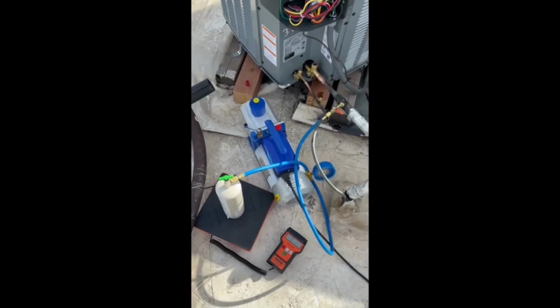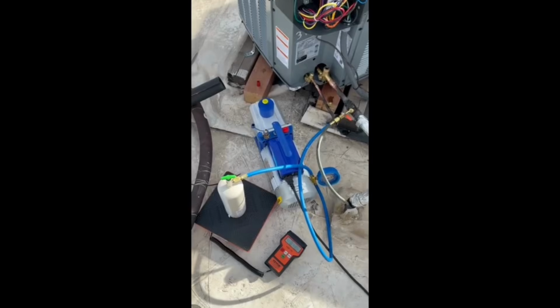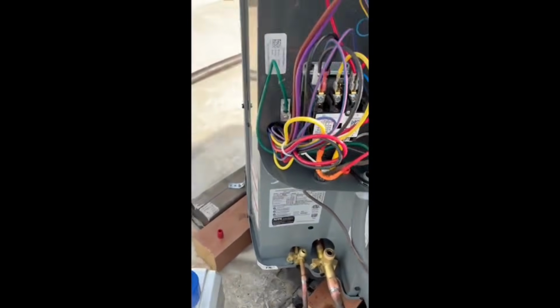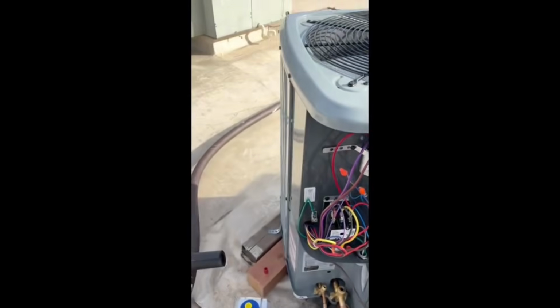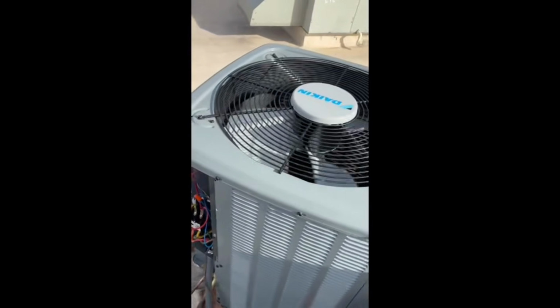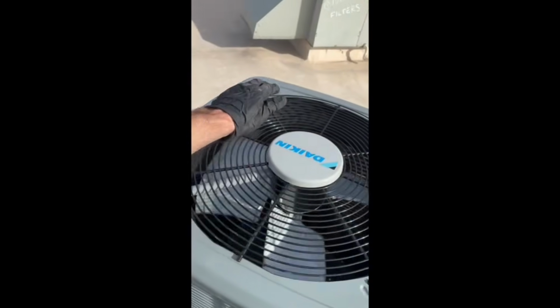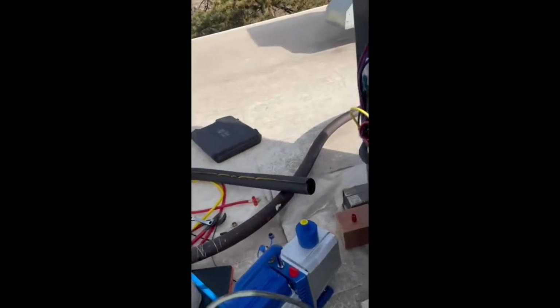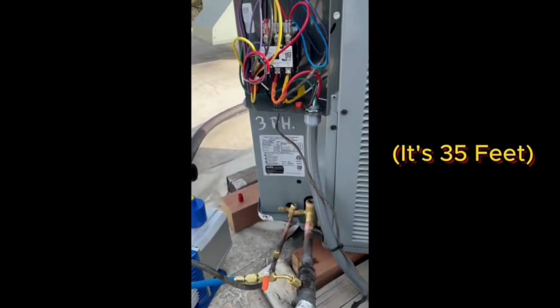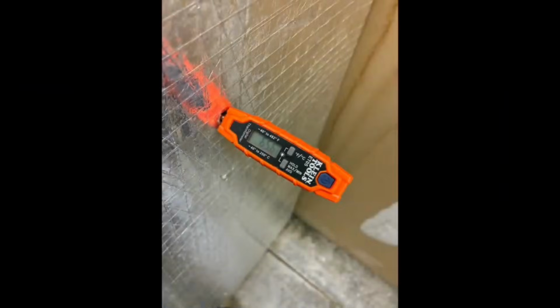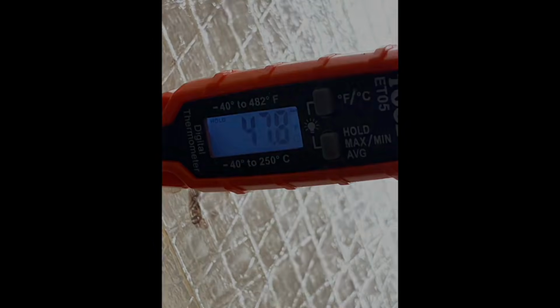Then I'll flip on the unit and make sure that everything's spinning in the proper direction. And I did an amp check with my clamp-on amp meter on all three hot legs going to the compressor. Condenser cooling fan spinning properly. And because this line set is longer than 15 feet, I had to add about a half to 3/4 of a pound of refrigerant. So we're doing a check. We got 65 degrees here on our return and 47 on our supply. That's downstairs at the air handler.